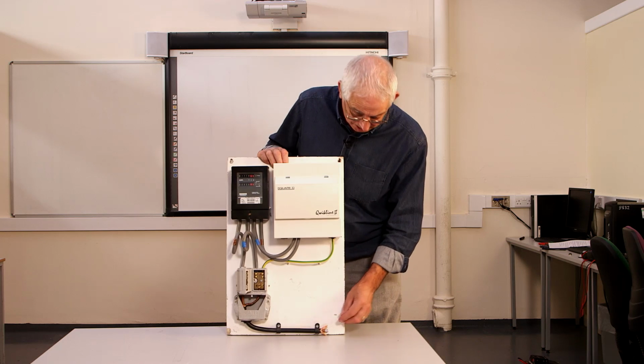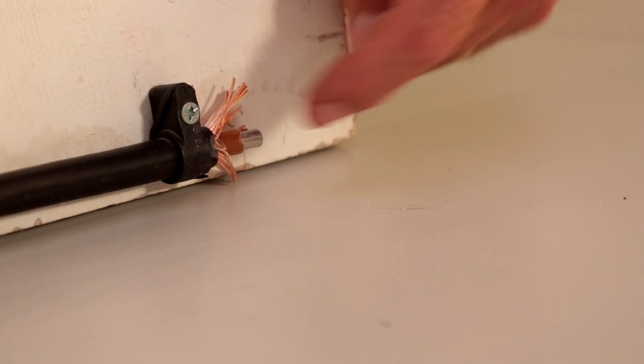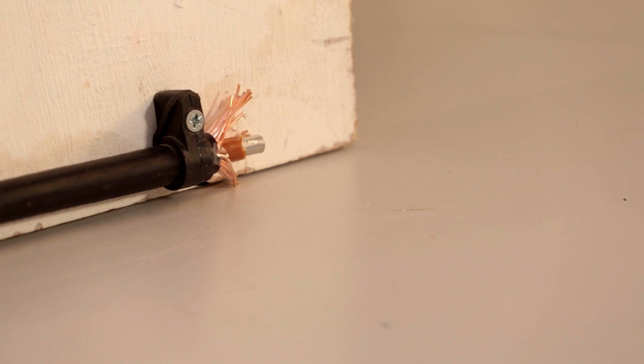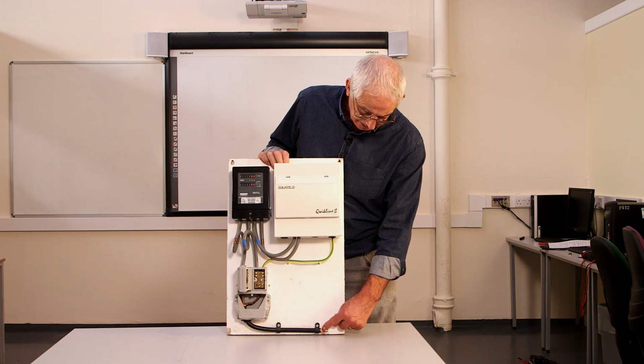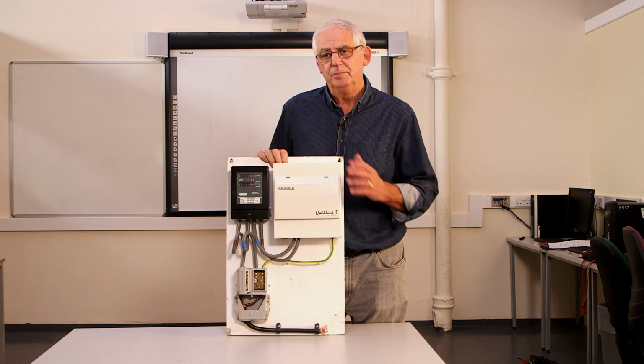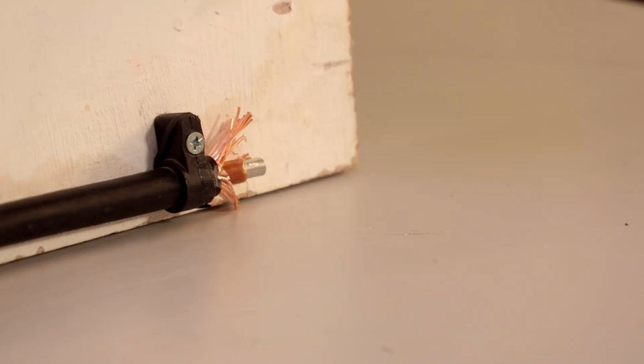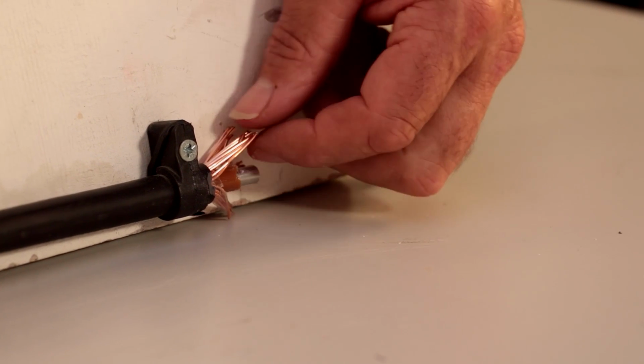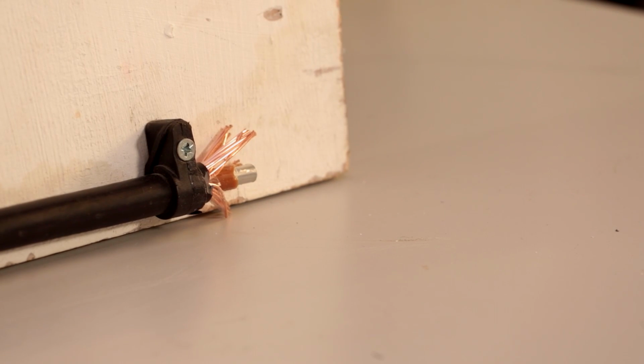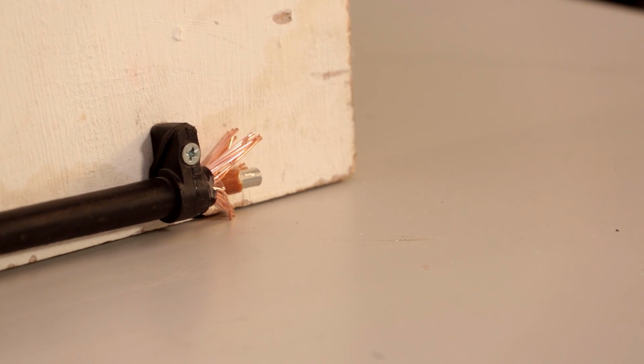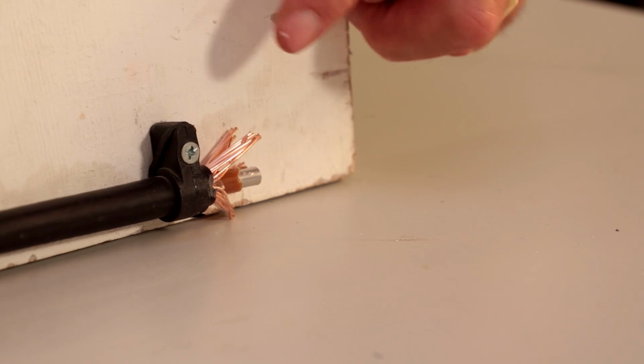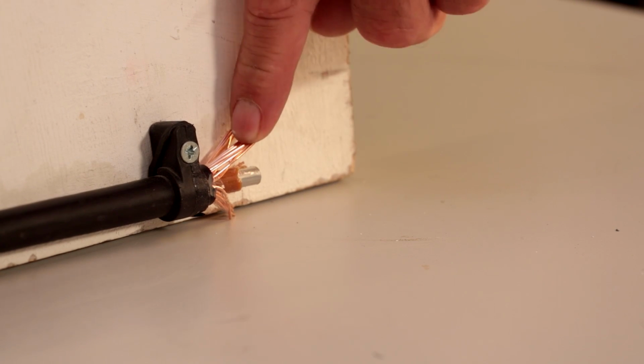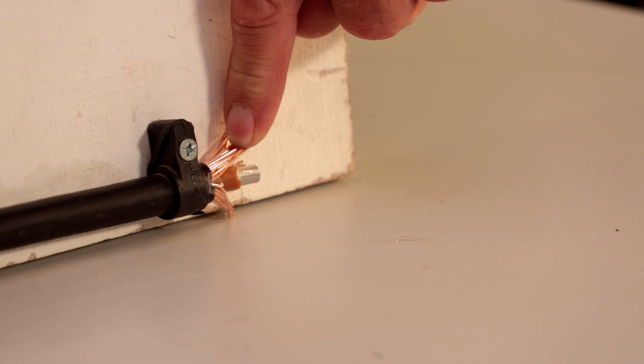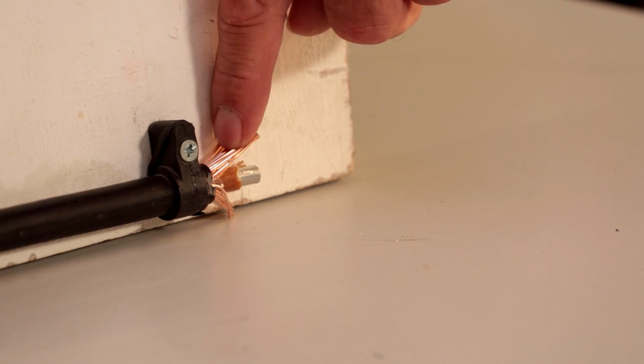And if you look, you can see here, the inner core is just a solid aluminium conductor. That's encased by PVC insulation. And then around the outside is wrapped a copper. It's almost like a steel wire armour, but it's copper. And it's literally, it forms the outer core. And this conductor here is the one we would call the PEN conductor, because it does the earth as well as the neutral.